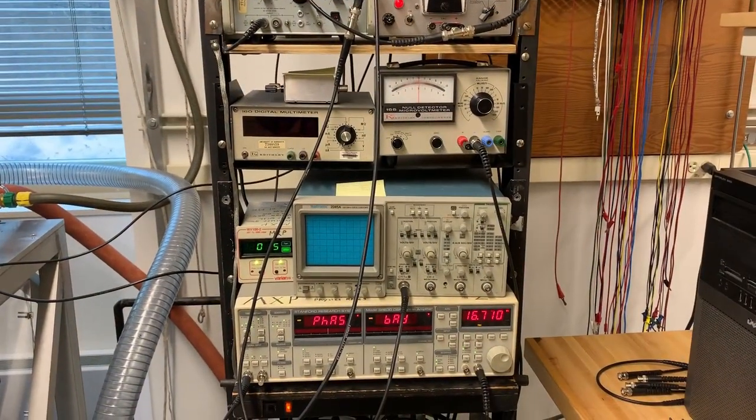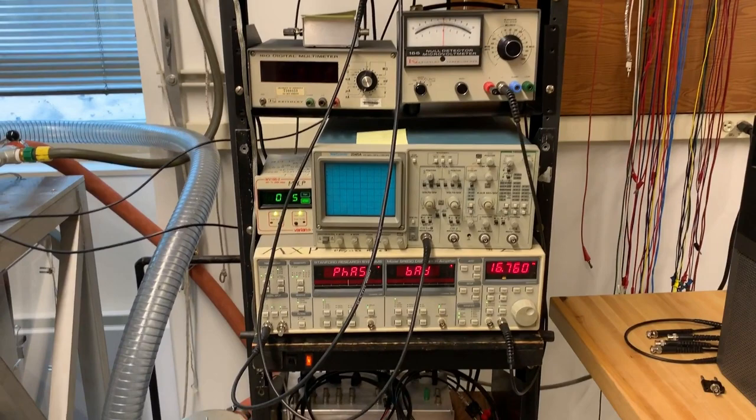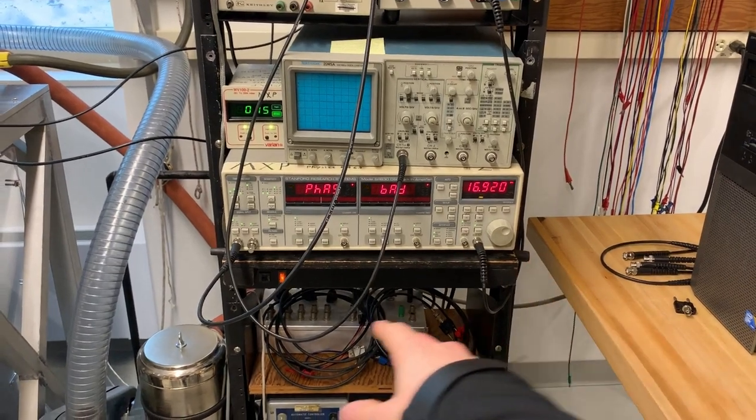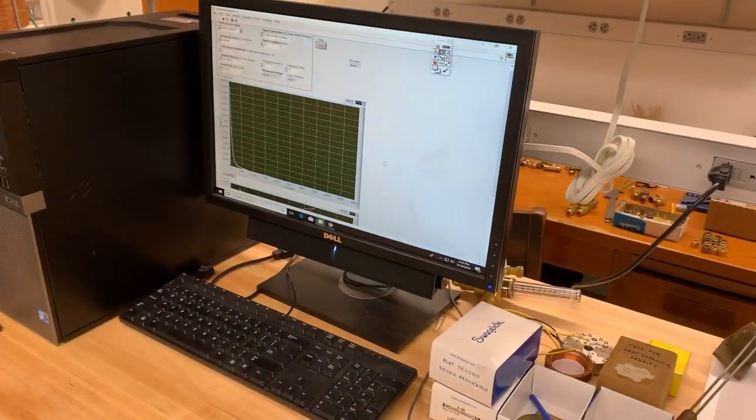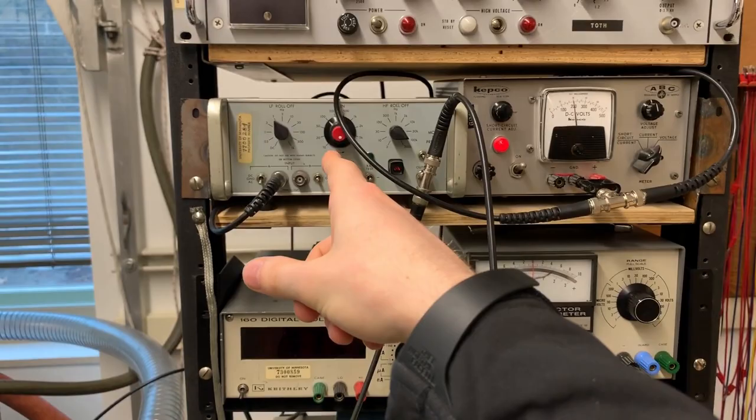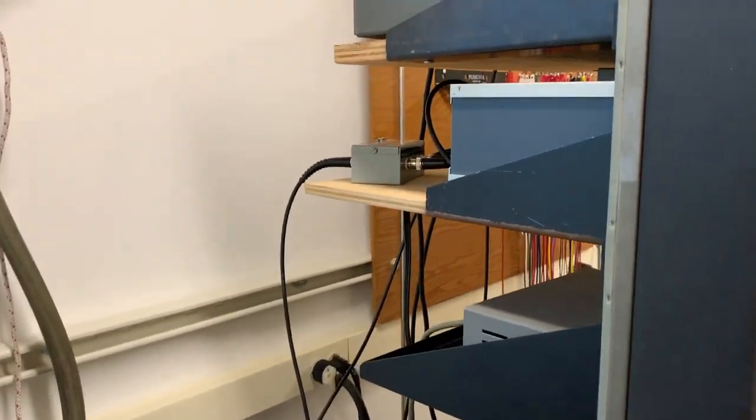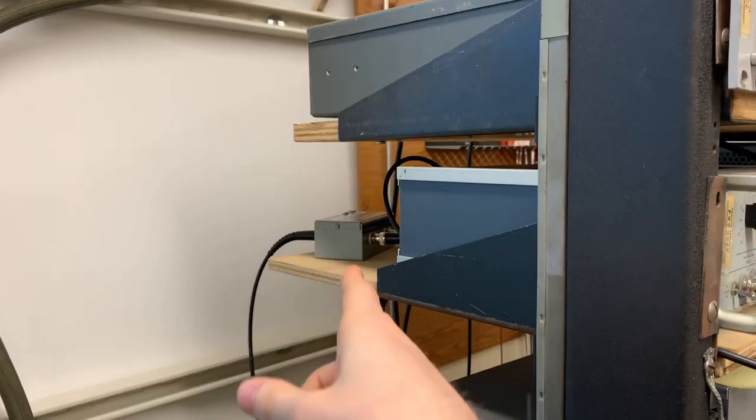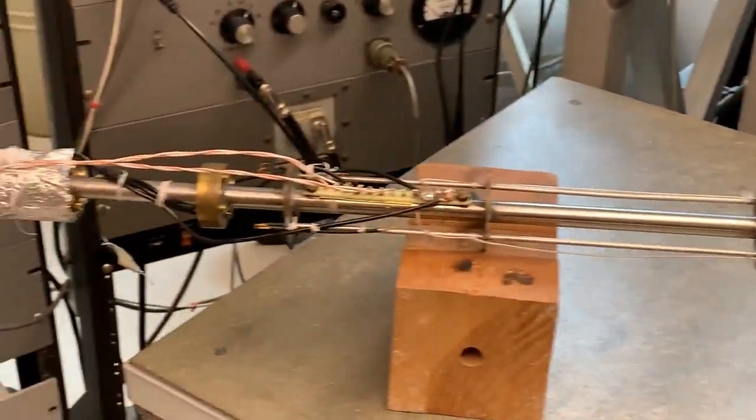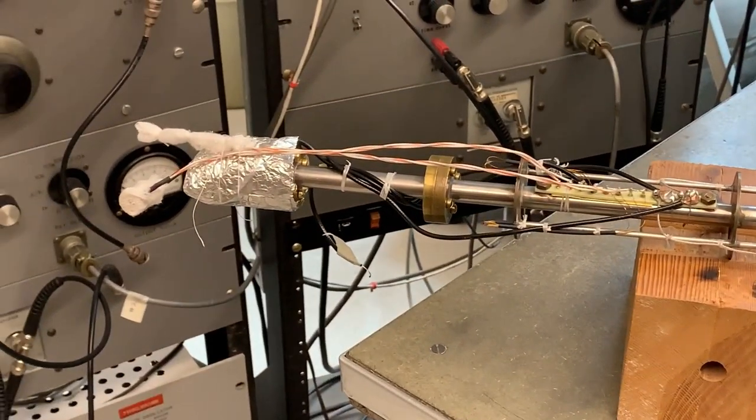Now I'm interested in showing you the equipment actually on the rack. This is the lock-in amplifier that we're dealing with, that's the one that contains the frequency generator and the detector, obviously that's the computer it sends the data to, and it has the LabVIEW program that's controlling the frequency generator. This here is that preamplifier you saw on the diagram. This is the DC bias voltage source, then all those resistors and capacitors that play a role in the filtration are in there, and one other box, one each for the detector and the driver. This of course is the cryostat with the resonator at the end, and that is active right now.